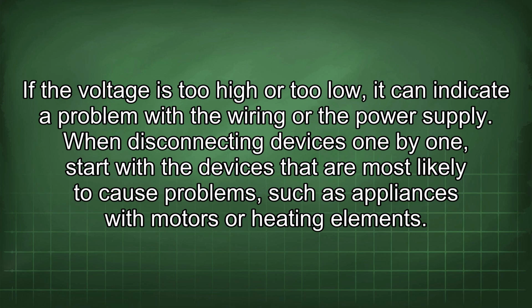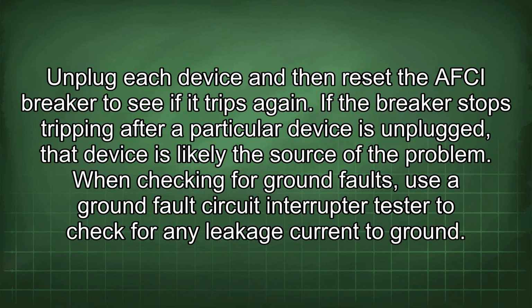When disconnecting devices one by one, start with the devices that are most likely to cause problems, such as appliances with motors or heating elements. Unplug each device and then reset the AFCI breaker to see if it trips again. If the breaker stops tripping after a particular device is unplugged, that device is likely the source of the problem.